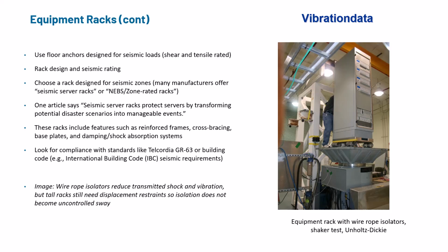So, equipment racks. Here's an interesting console or rack mounted on wire rope isolators, attached to a head expander, which is then mounted to an Unholtz-Dickie shaker. Now, wire rope isolators—I fully support that idea, but there's more to the story, because we need to make sure the displacement is limited. There still need to be braces, restraints, or snubbers of some sort so that the sway doesn't become too large, particularly at the top of the rack.